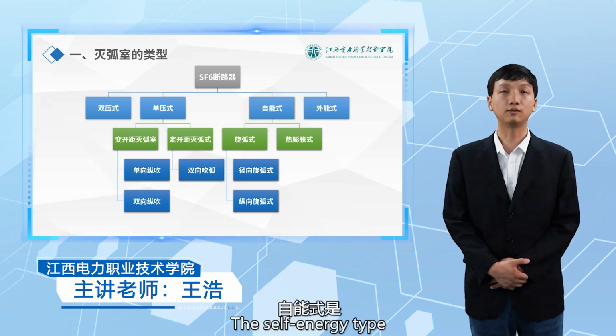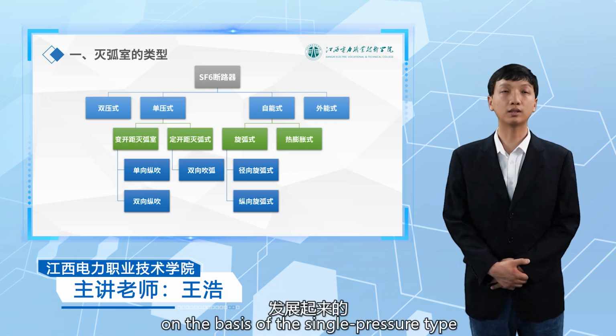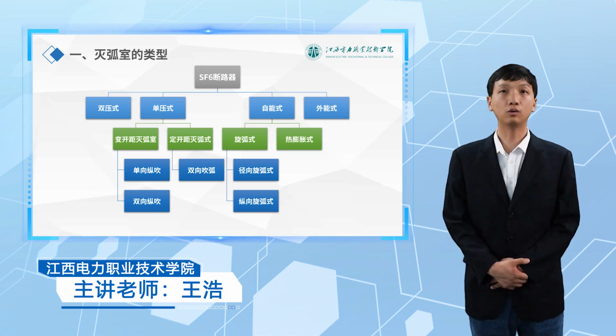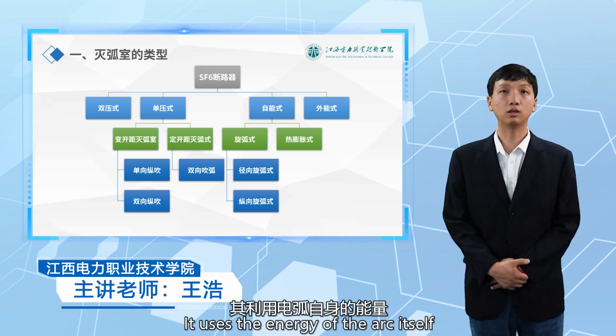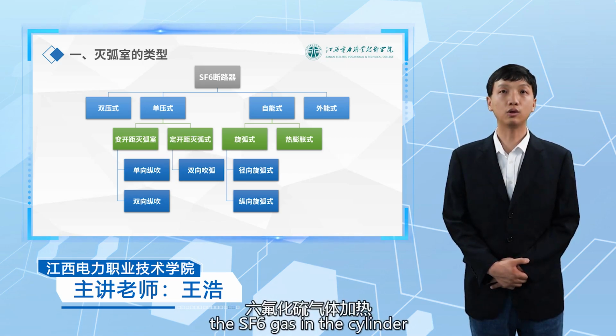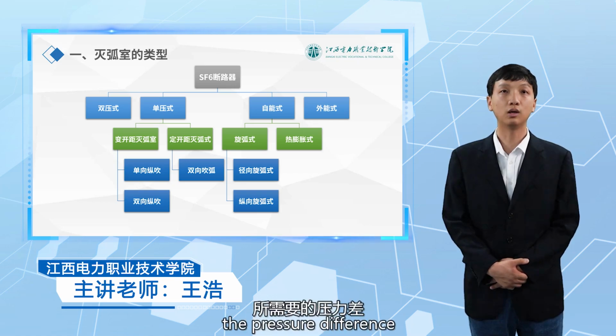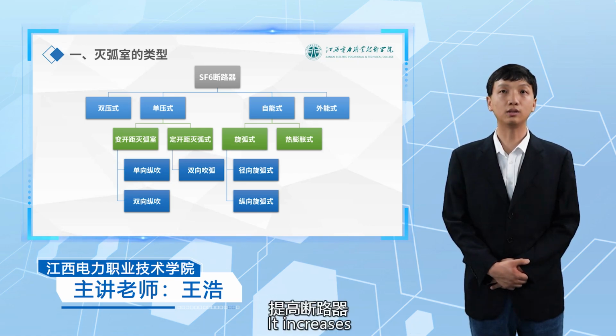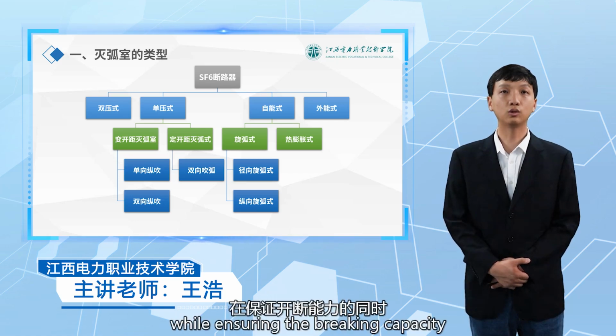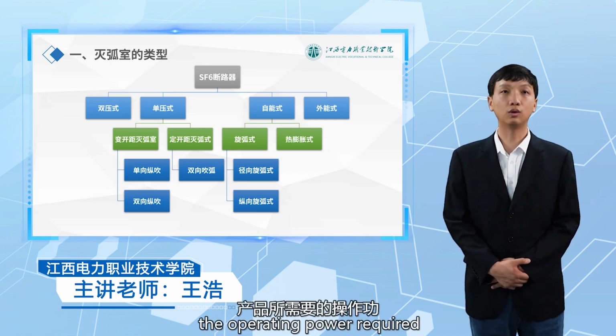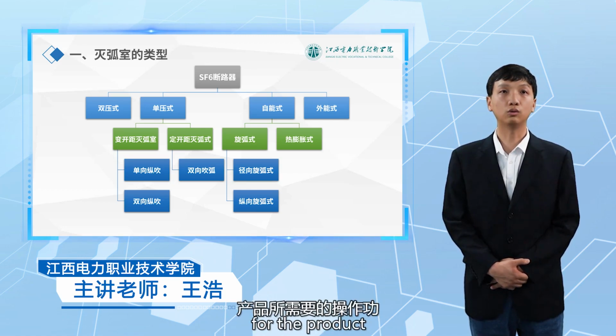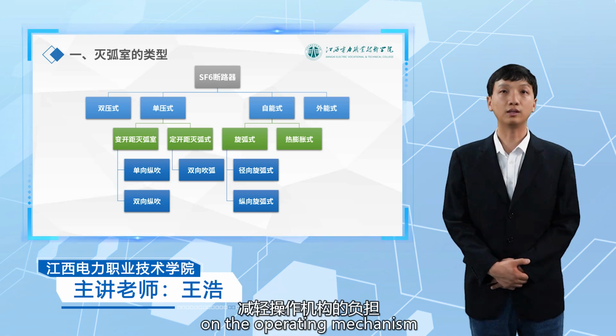The self-energy type is developed on the basis of the single pressure type. It uses the energy of the arc itself to heat the sulfur hexafluoride gas in the cylinder, creating the pressure difference needed for arc extinguishing. It increases the arc blowing pressure at the current zero crossing while ensuring the breaking capacity and minimizes the operating power required for the product, reducing the burden on the operating mechanism.